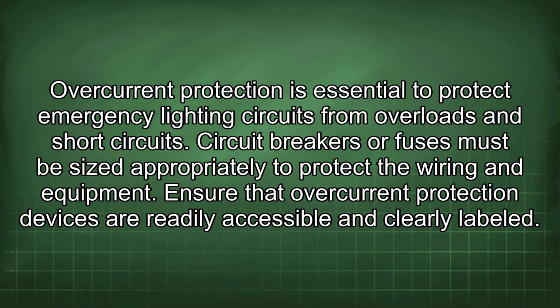Overcurrent protection is essential to protect emergency lighting circuits from overloads and short circuits. Circuit breakers or fuses must be sized appropriately to protect the wiring and equipment. Ensure that overcurrent protection devices are readily accessible and clearly labeled.